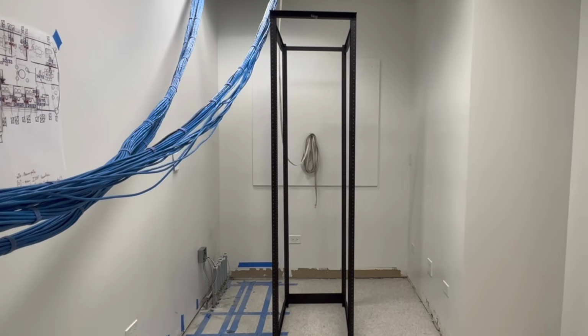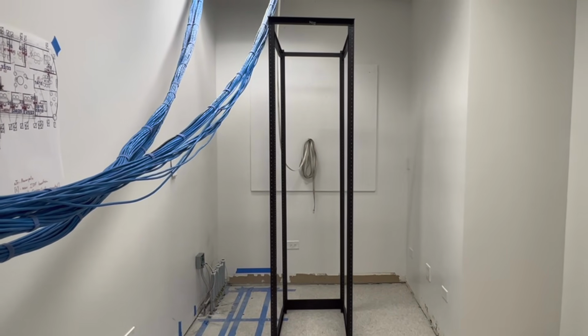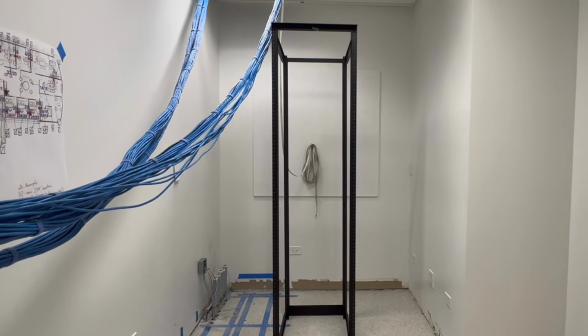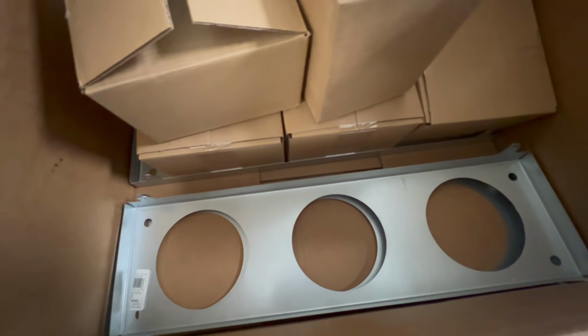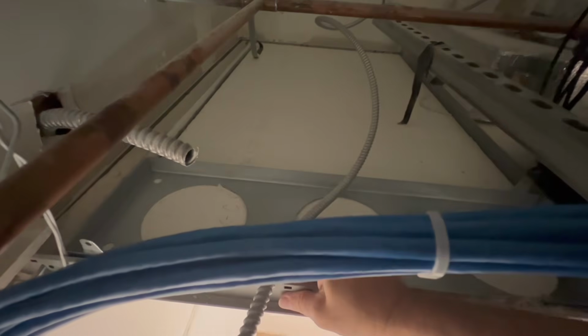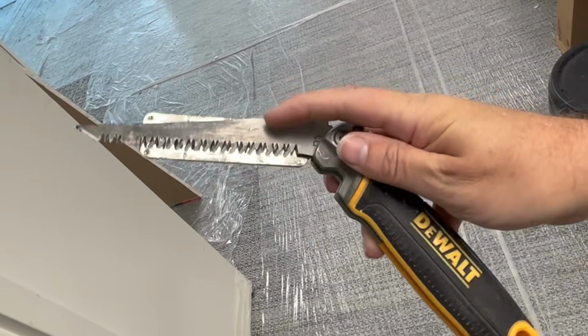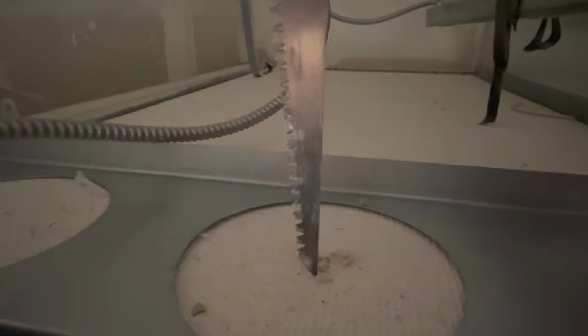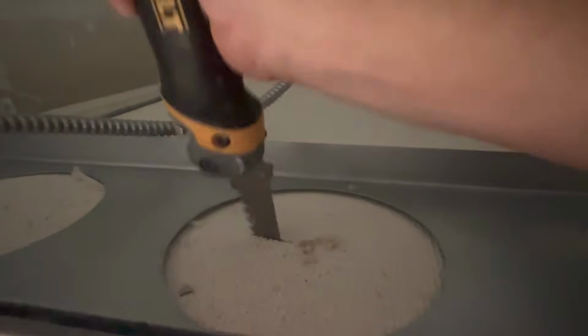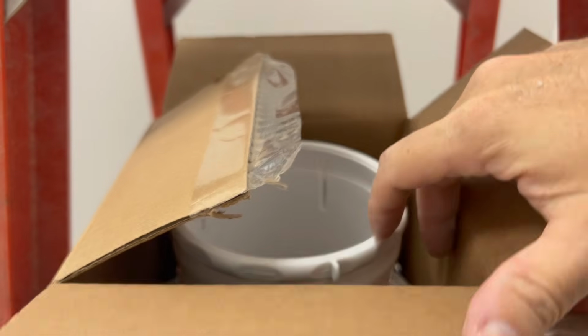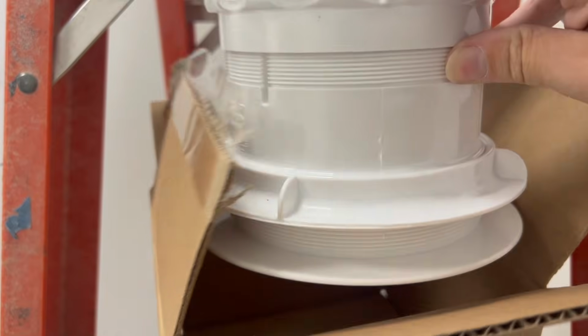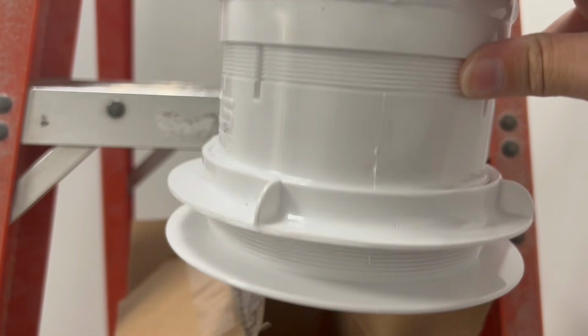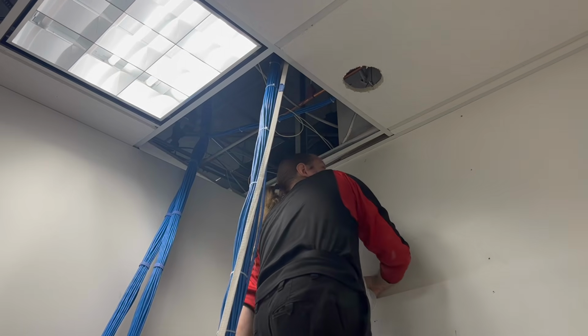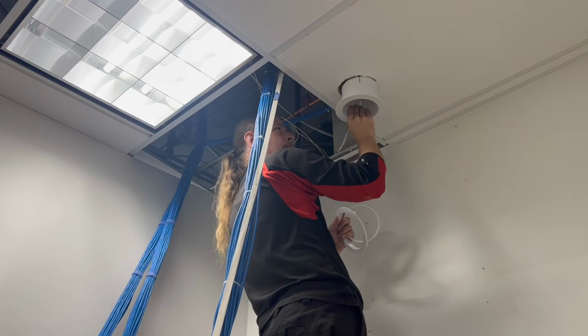With the cables somewhat organized, it's time to get them down out of the ceiling and into our rack. This ceiling interface system rests on top of our drop tiles. We'll use a jab saw to cut a hole in the tile matching the hole in the metal outlet, then get one of our riser tubes from the box. It screws in from the bottom and top, locking in to create a grommet or pathway from the ceiling toward our rack.